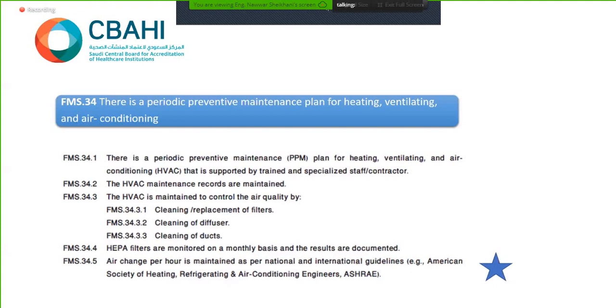HEPA filter locations, where? We locate HEPA filters usually in the operation theater, on the supply over the operation table. We have HEPA filters in procedure rooms, in C-section, in cath lab, in isolation rooms. We look at the HEPA filter on the return, not on the supply, of course, in isolation rooms. We have it in CSSD as well, and in miscellaneous locations.